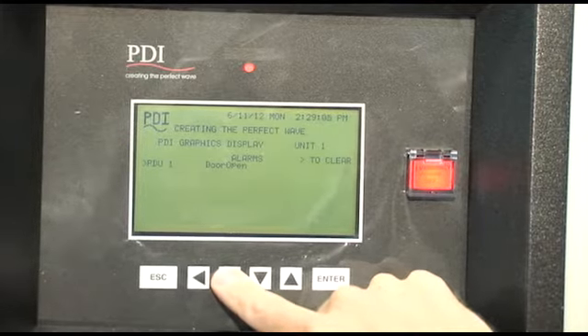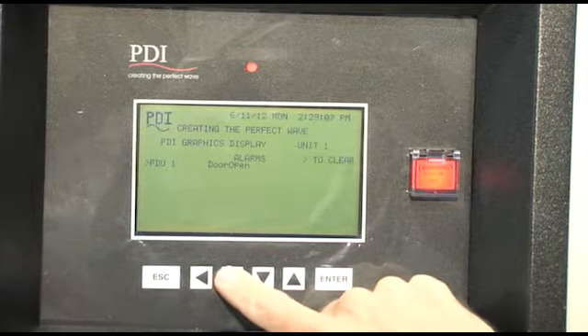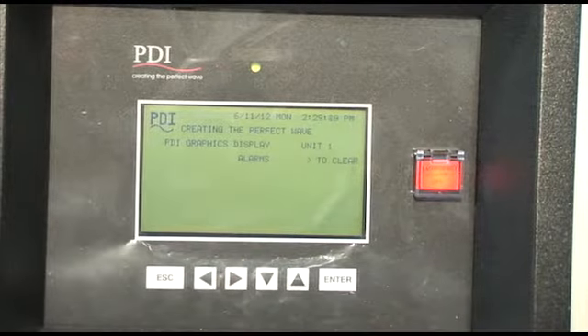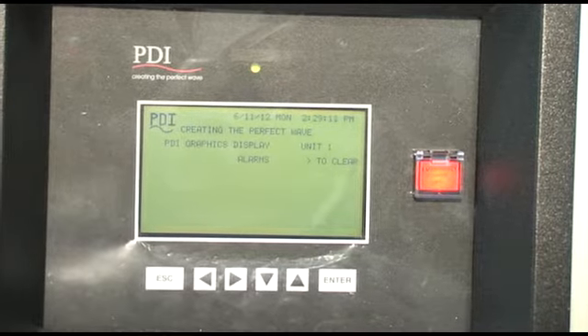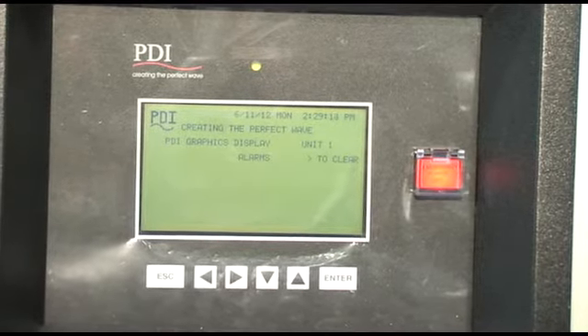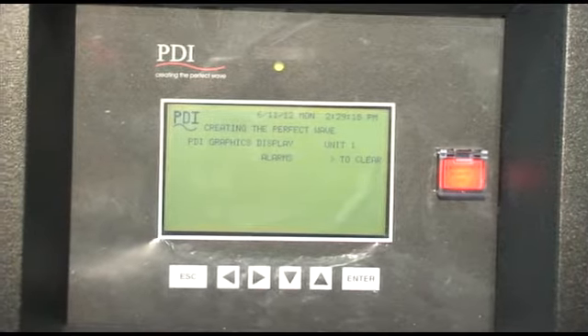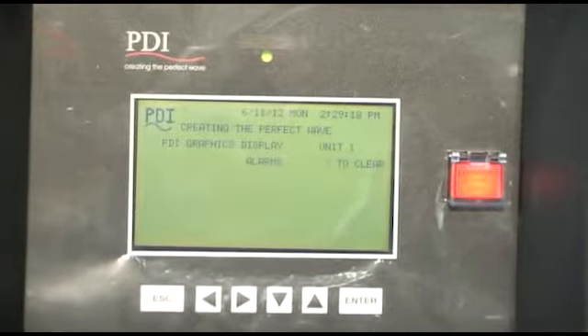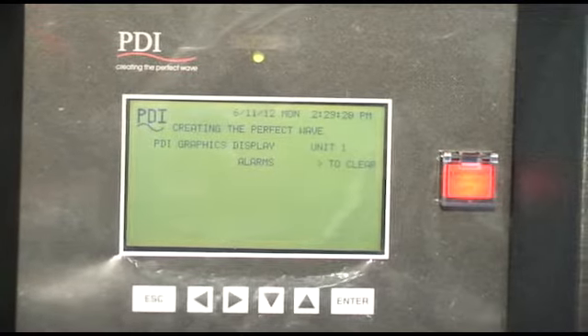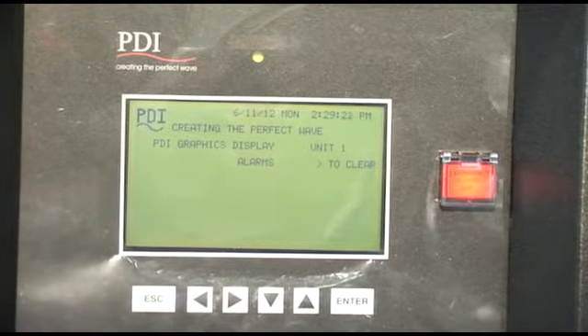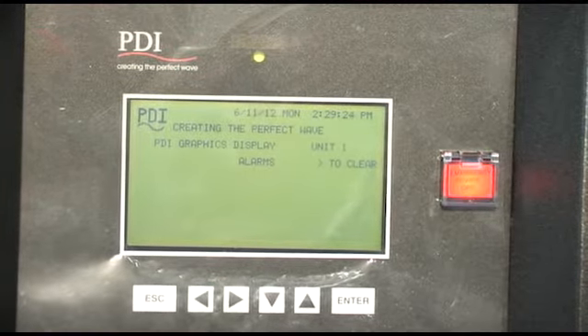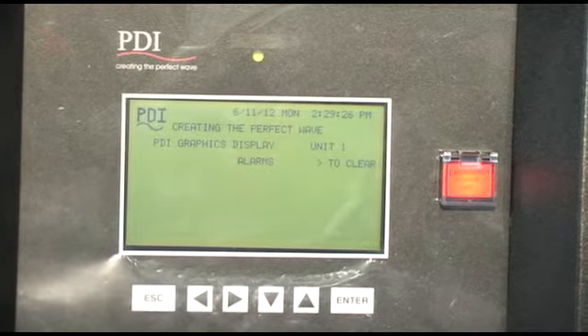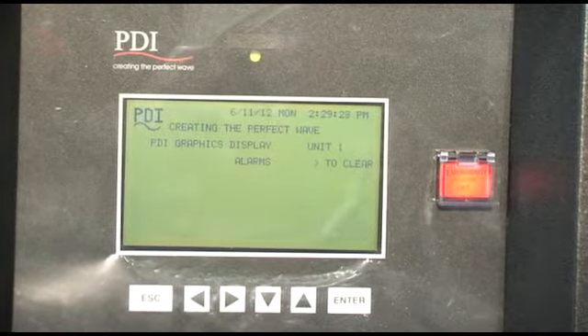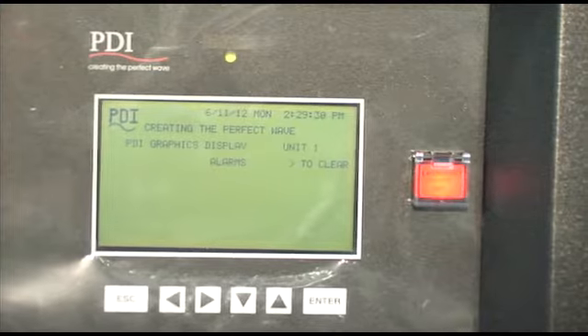You may see the LED turn red or even yellow. If you see other than green, it's usually an indication of an overcurrent alarm. And you can go over to the remote power panels and you can check either there or from your remote communication system as to which circuit has had an overcurrent in the past. Usually it will have a record of the highest current that it has had for any particular circuit.